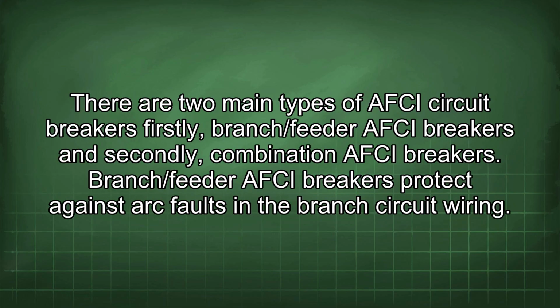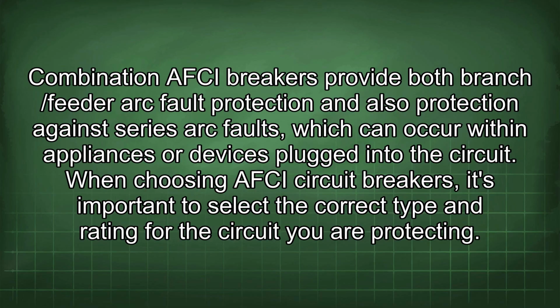There are 2 main types of AFCI circuit breakers. Firstly, branch/feeder AFCI breakers, and secondly, combination AFCI breakers. Branch/feeder AFCI breakers protect against arc faults in the branch circuit wiring. Combination AFCI breakers provide both branch/feeder arc fault protection and also protection against series arc faults, which can occur within appliances or devices plugged into the circuit.